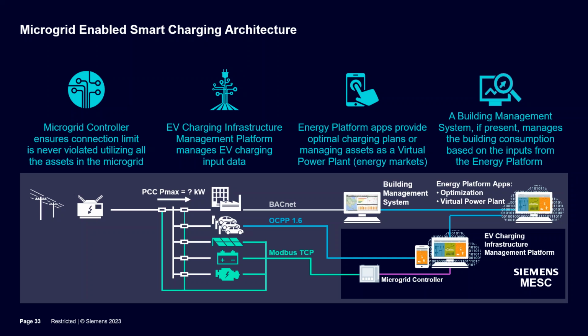One way to mitigate that is through what we call microgrid enabled smart charging. If we need a new transformer or a new distribution feeder to serve that load, we could be looking at years. Right now the lead time on medium voltage, high voltage gear is scary, and it's expensive too. So if the utility tells us it'll take 2 years and millions of dollars to serve the load we want on the feeder, we need to look for alternatives. Microgrid controller enabled smart charging is one such alternative.